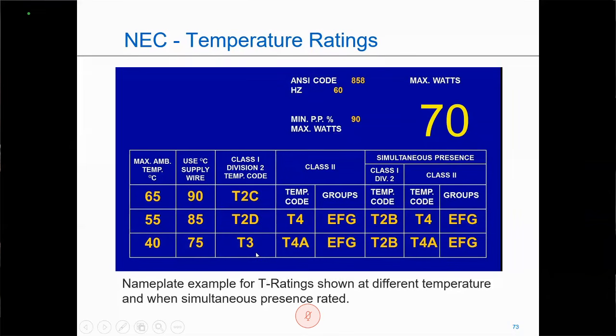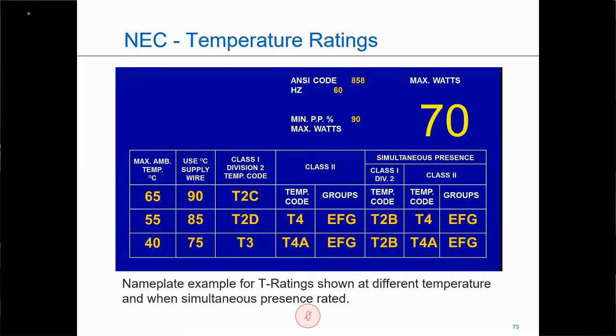So here gives us an example. Remember, the closer you are to T6, the better. The closer you are to T1, the hotter. T3 temperature rating, 55 degrees C, T2D. Temperature rating as I go along. Under simultaneous presence, yes. Okay, certainly. So at 40 degrees C, my temperature rating is a T3. When the air gets warmer, my fixture's not dissipating the heat as well. So at 55 degrees C, my temperature rating isn't quite as good as a T2D. And at the next step, again, the air's a little warmer. My ambient air's warmer.